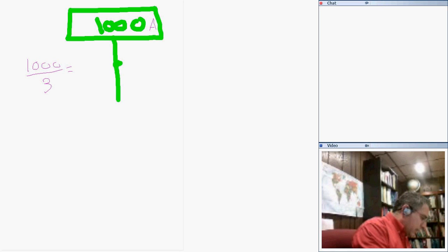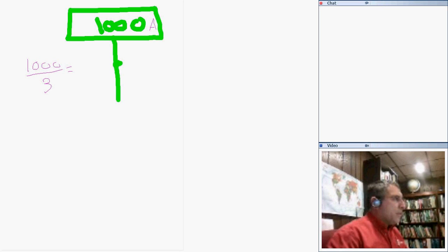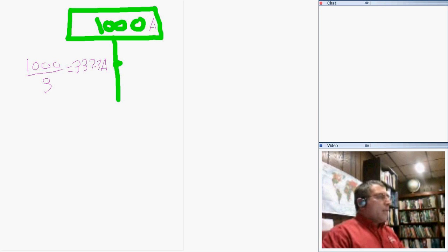So take 1000 divided by 3 runs, and that'll get you 333 amps. When you want to parallel, you want to stay with my rule. You stay within the 300 range, because 500 kcm can give you about 380 amps on average. Parallel in the 300s is the best application in my book anyway. So if we divide by 3, that's 333.